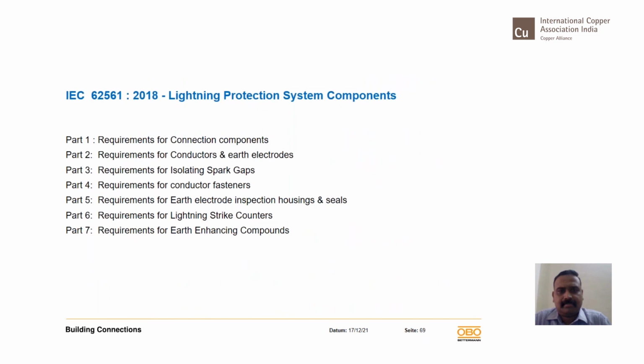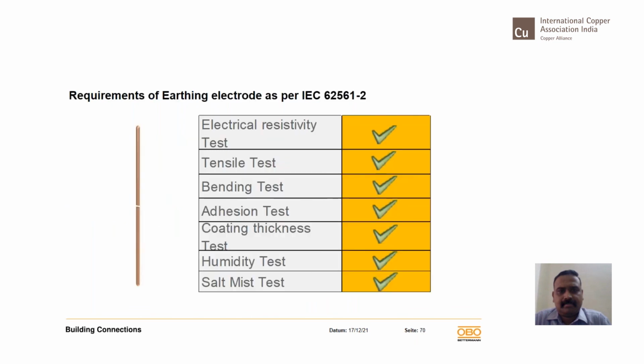The 62561 standard gives you the guideline for the test requirements of all these components, be it the lightning protection system, counter, earth pit chamber, or whatever. Especially for earth electrode and compound, part 2 talks about the test requirements of earth electrode, and part 7 talks about the test requirements of earth enhancement compound. For example, part 2 says if you are using a copper bonded steel rod, you need to have electrical resistivity, tensile, bend, adhesion, coating thickness, and humidity tests done. The first 3 tests ensure the rod is mechanically tested for its mechanical capabilities, and the rest of the tests ensure the corrosion resistance of the electrode.